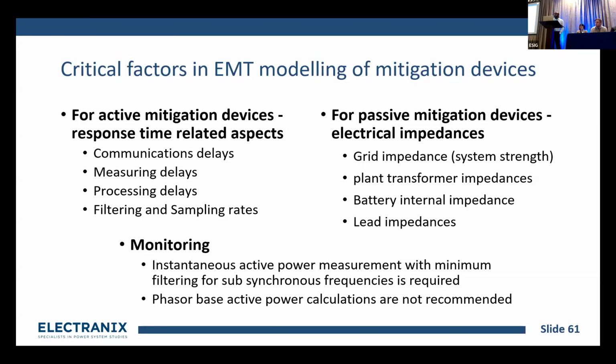And for the passive devices, as an example the double conversion ones and the GFM batteries, what is mainly important is that the impedance model is right. So you have your grid impedances and the plant transformer impedances, and especially the last two bullets, the battery internal impedances and the lead impedances. These two are also very important in a situation where you have a double conversion UPS. Your battery impedances and lead impedances will make your DC bus voltage not flat.